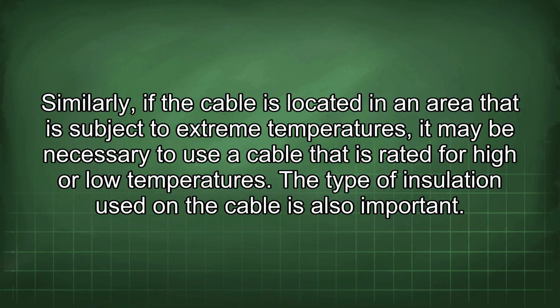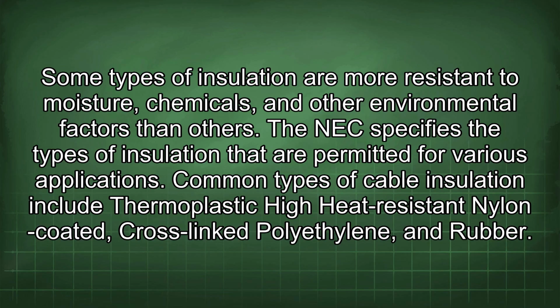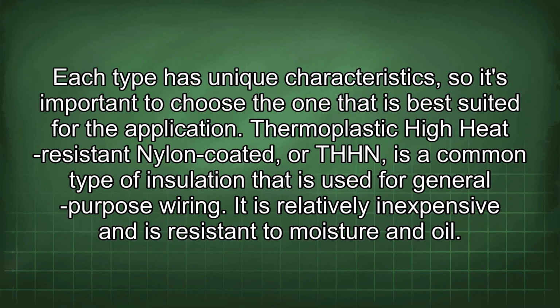The type of insulation used on the cable is also important. Some types of insulation are more resistant to moisture, chemicals, and other environmental factors than others. The NEC specifies the types of insulation that are permitted for various applications. Common types of cable insulation include thermoplastic high heat resistant nylon coated, cross-linked polyethylene, and rubber. Each type has unique characteristics, so it's important to choose the one that is best suited for the application.